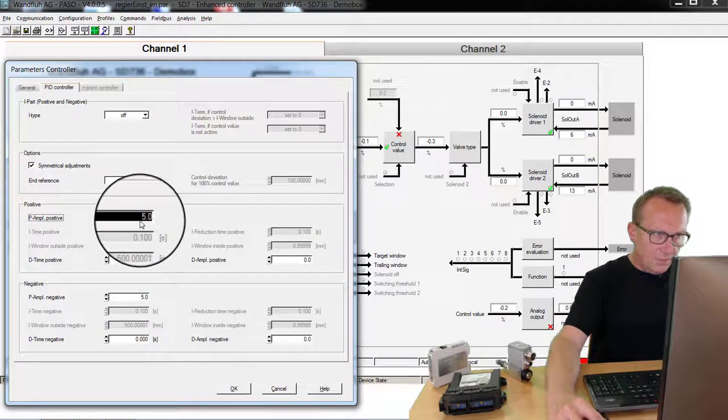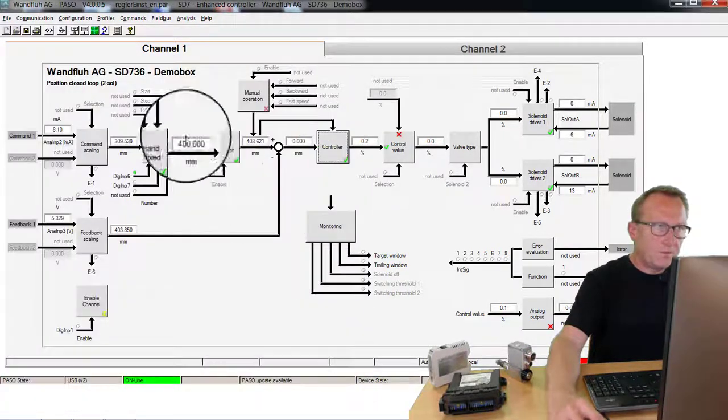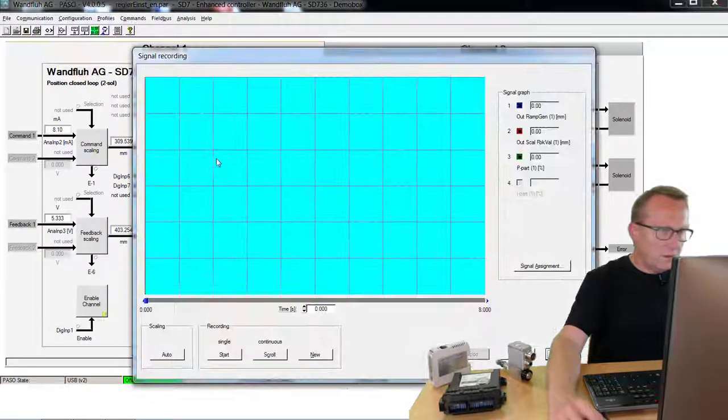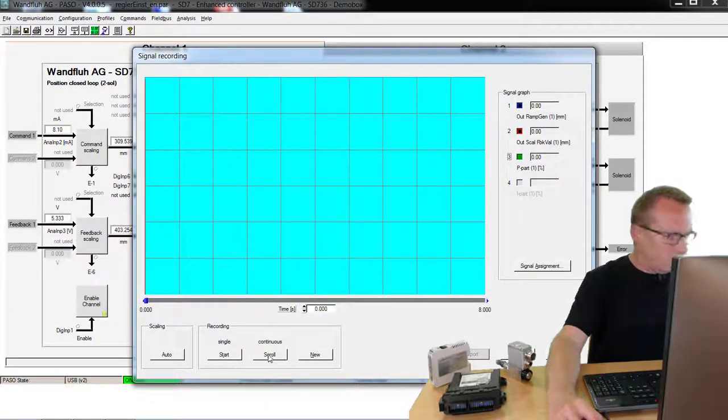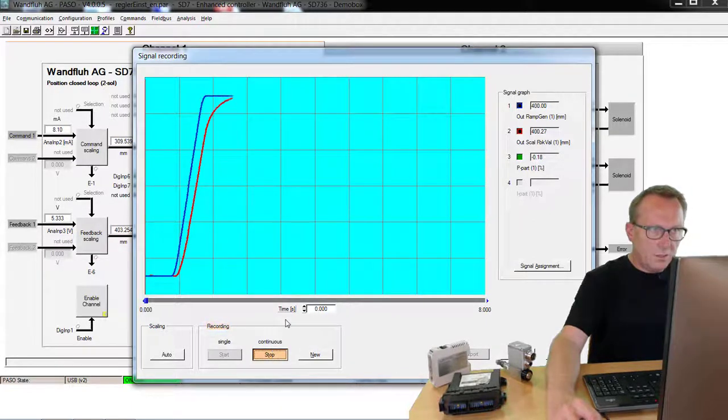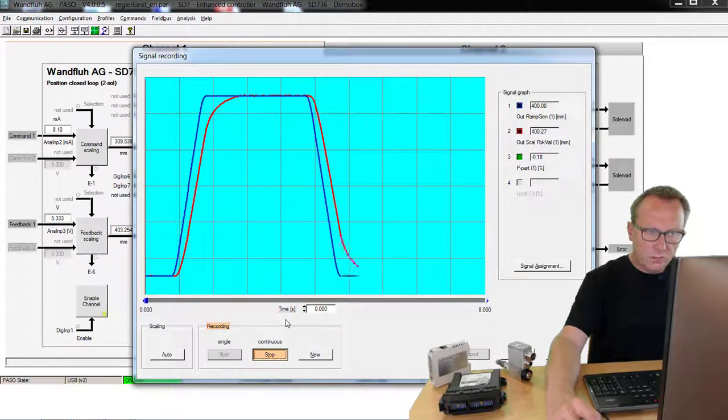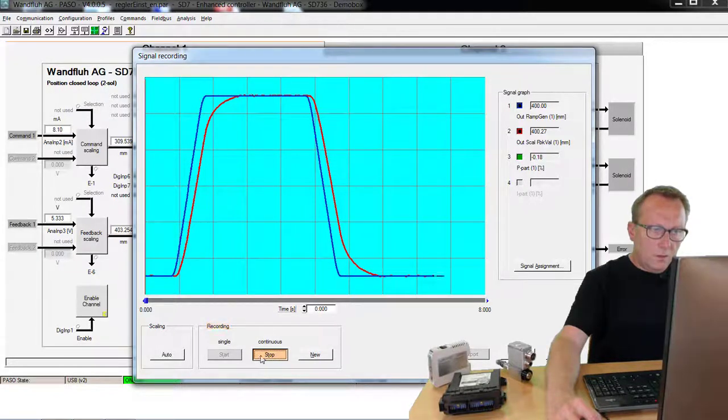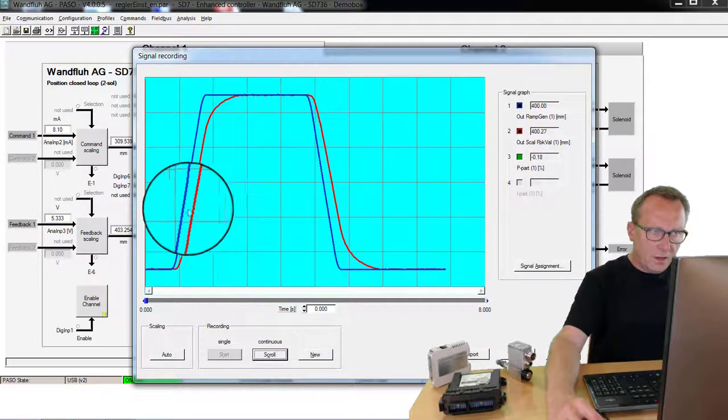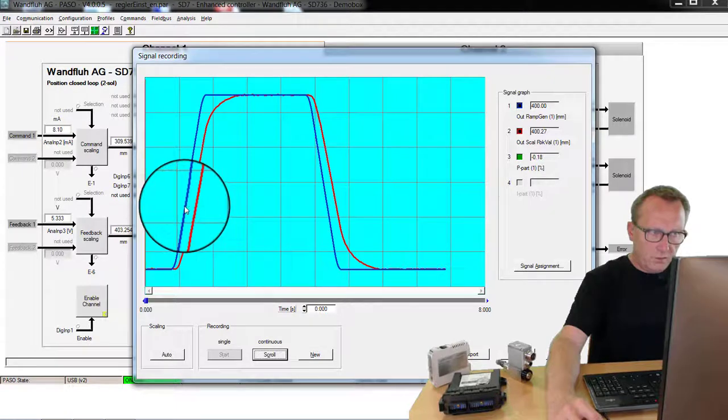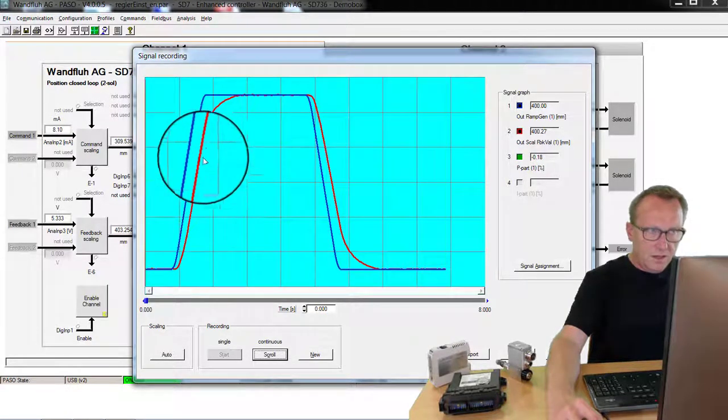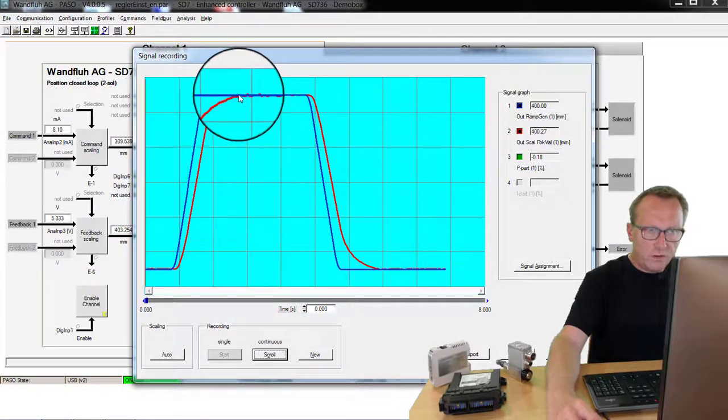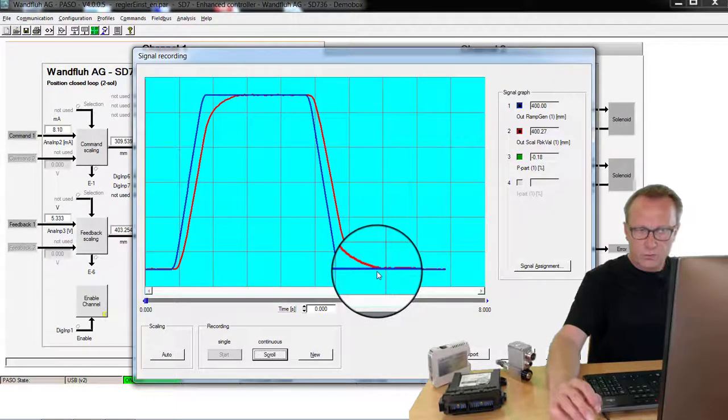For example when we set it to 5. We open the signal recording. We start the recording. Now we see my system moves from one to the other position. But you can see that we have a big deviation between command and feedback. And the cylinder moves very slowly into the end position.